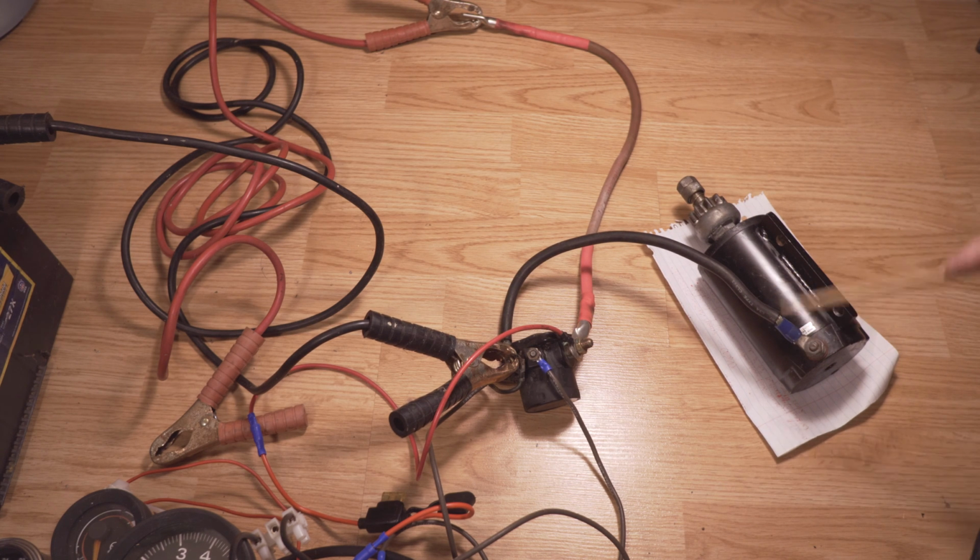And what often happens is these cables, for example under the plastic cover, get slightly rusted, and the cable itself may appear like it's fine, but it really isn't, and it's not giving it quite enough current to work properly. So you may have a situation where it's working sometimes and not other times, or when the cable moves a little bit, it's not working.